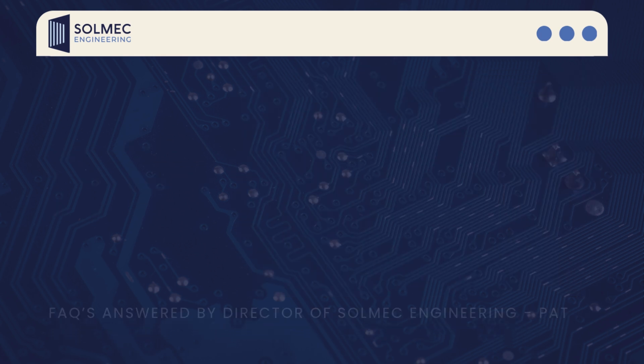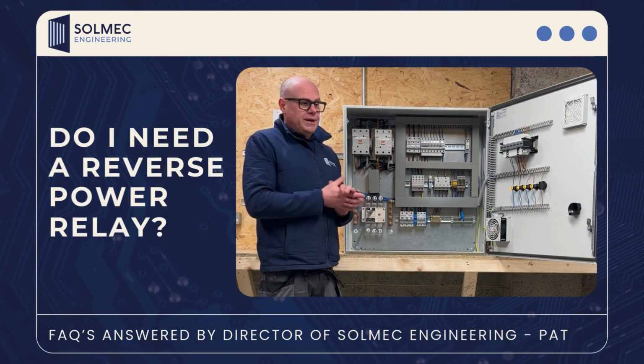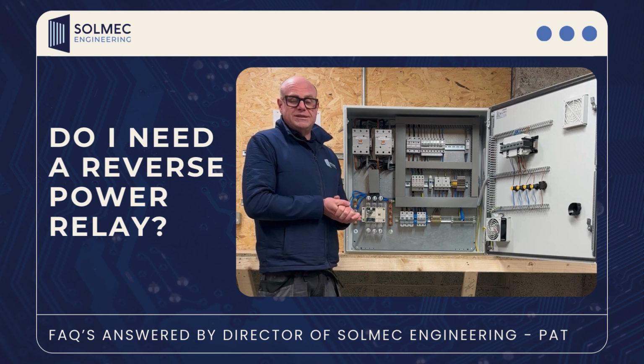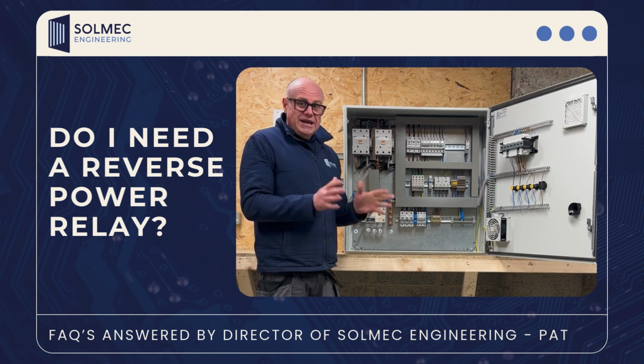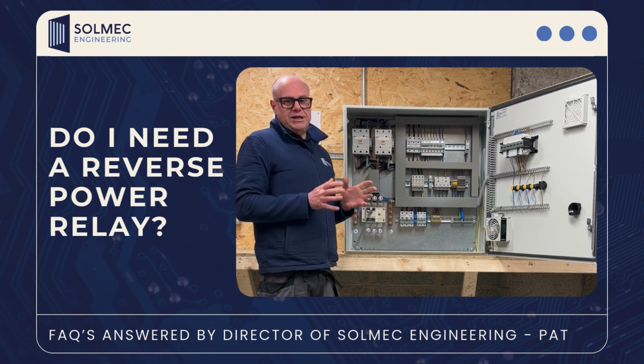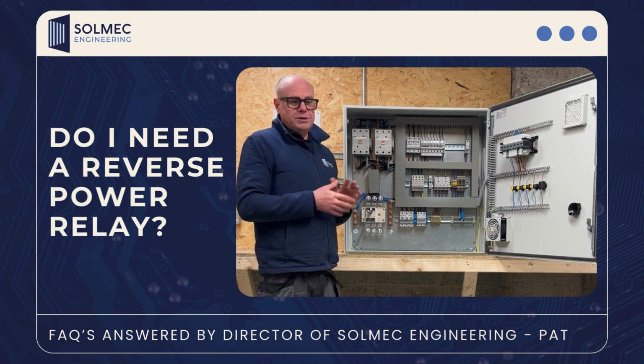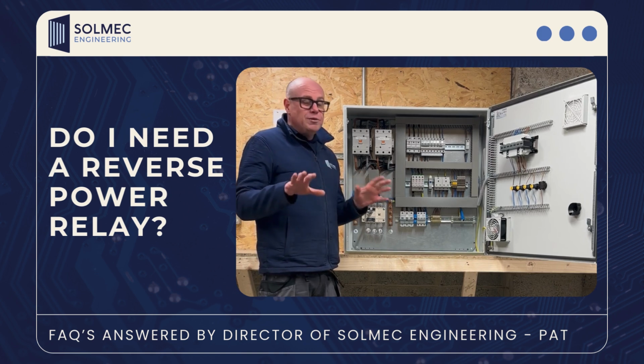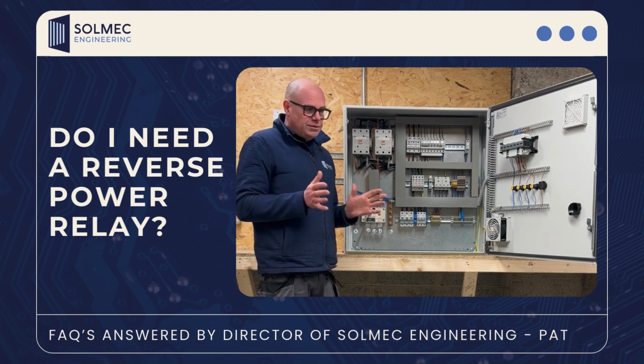In one of the other videos I've done, I got a couple of questions about reverse power relays. You don't actually need a reverse power relay in small scale generation between 50 and 200 kilowatts. When you go above 200 kilowatts, there are some requirements for a reverse power relay, but not always either.